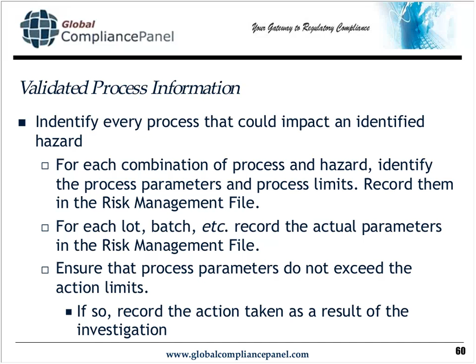Now, the other place that we're going to look at is post-production information and risk management, and oftentimes this is going to show up in the complaint system. So you're going to evaluate every complaint against the probability of occurrence and the severity of harm to see whether or not it matches what you did in the risk management file, and you're also going to do an evaluation in 820.100 in which you're going to analyze complaints using appropriate statistical techniques.